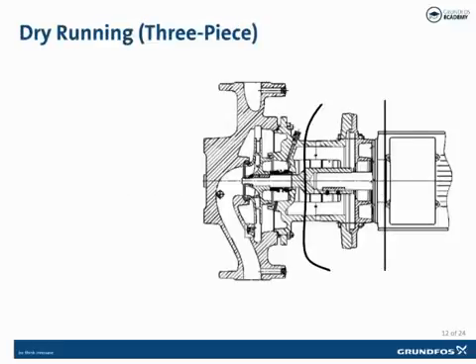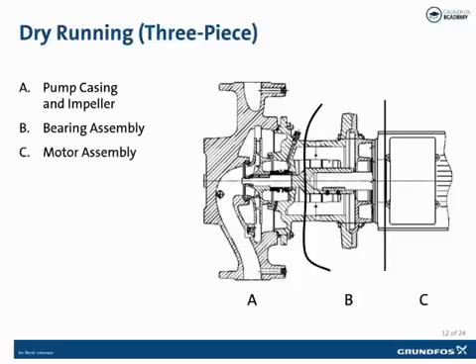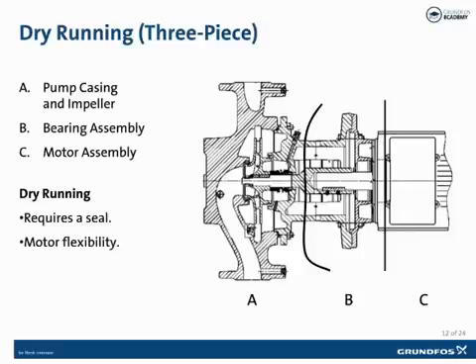There are two main types of inline pump units. The first is the three-piece or dry running pump. The three pieces refer to the pump casing with the impeller, the bearing frame, and the motor. Dry running means the liquid does not contact the motor — it is sealed with a mechanical shaft seal inside the casing. Three-piece pumps have interchangeable motors, providing application flexibility with a wide range of flow and head combinations from one pump body. They are also repairable, with individual components replaceable should any fail. Proper shaft alignment is necessary for long life and bearings usually require annual service. Three-piece pumps are typically more expensive than one-piece pump types.